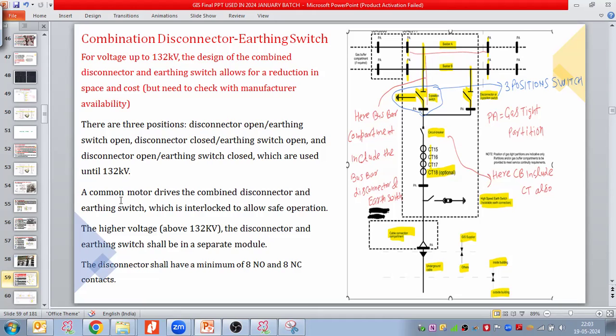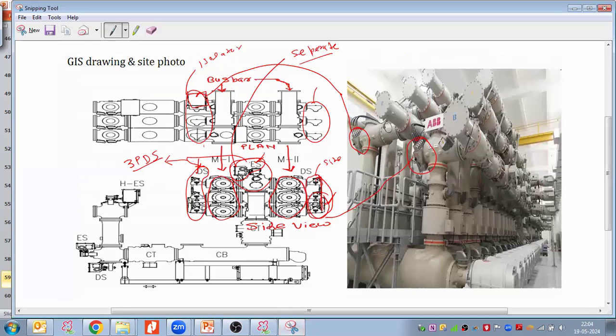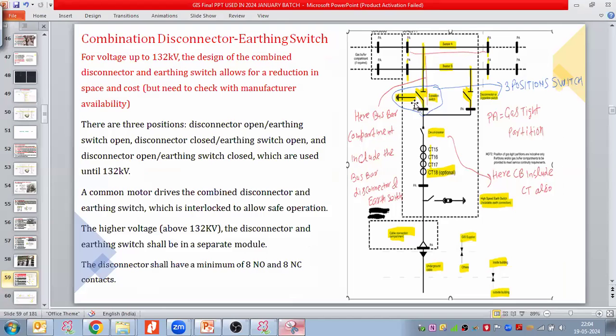These are the 3 positions used up to 132 kilovolts. A common motor drives the combined disconnector and earthing switch, which is interlocked to allow safe operation, so mechanical interlocking is easily possible here. This kind of arrangement is safer because mechanical interlocking is directly possible. In the arrangement where the disconnector and earthing switch are in separate modules, mechanical interlock may be difficult and only electrical interlock would be possible. But with the 3PDS arrangement, both mechanical and electrical interlocking are possible.